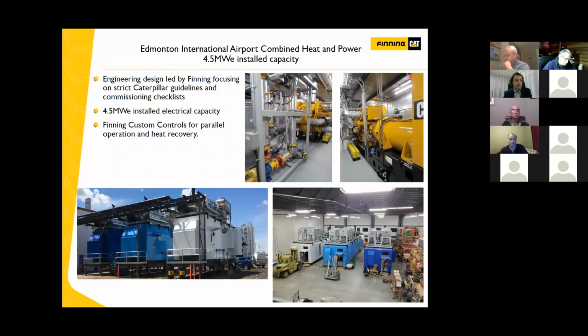Where Jim left off, I'll add some CHP examples here for us. On this particular slide, we have our combined heat and power site at Edmonton International Airport. We have installed electrical capacity of 4.5 megawatts. Engineering design was led by Finning, focusing on strict Caterpillar guidelines and commissioning checklists, as it says right there. This site consists of three high electrical efficiency Caterpillar G3512H generator sets, each having 1.5 megawatt electrical output.